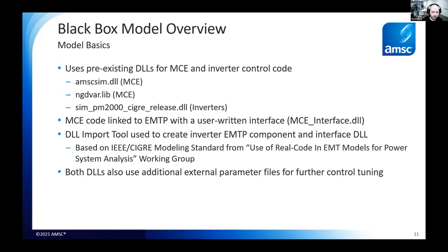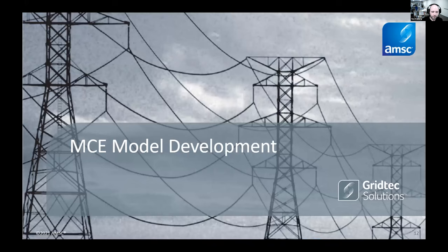Both models — for the MCE and for the inverters — also use additional external parameter files for non-standard parameters or parameters that aren't usually changed. There are simply too many parameters to bring them all into the EMTP user interface, and it's not really practical to expect users to fully understand all of them. Starting with the MCE, the high-level controller has inputs for voltage and current measurements, plus inputs for references such as voltage reference, power factor reference, reactive power reference, or commands from an external controller.